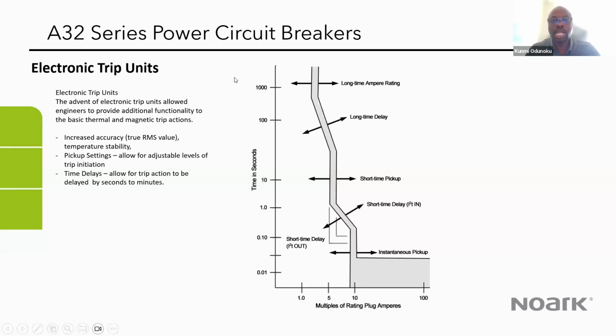You can introduce time delay for the long time protection, which is the overload. You can also introduce delay for the short time pickup, and also the instantaneous pickup. So basically, the electronic trip unit is a more advanced, more reliable way of offering protection to a circuit breaker. Typically it's a module that is detachable from the breaker itself in most cases. You also have some manufacturers that have the electronic trip unit embedded into the circuit breaker itself.